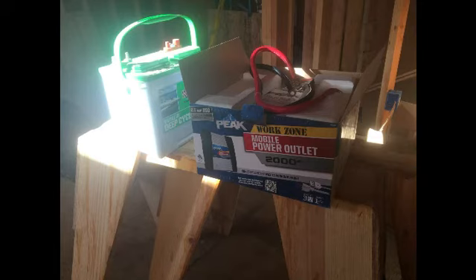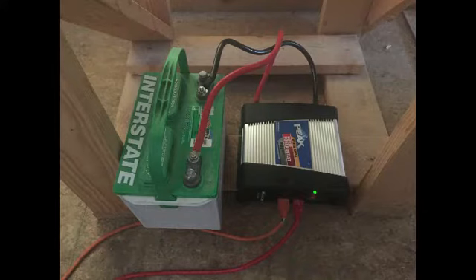You will wire the generator up to the neutral side of the panel box and also the positive bus. You will have 2 positive buses, one for 110 and the other is also a 110 volt, which would combine to make 220 volts for your appliances that need those, like an electric range or electric dryer, things like that. But first you want your generator to be grounded properly.